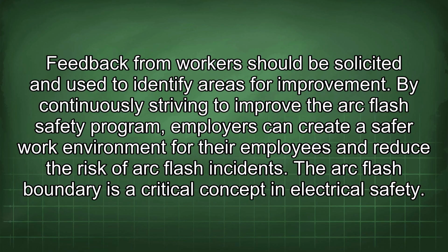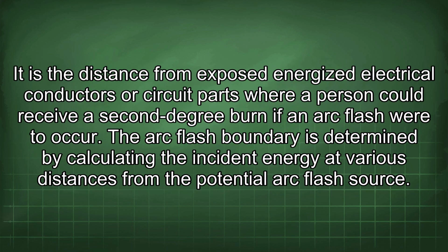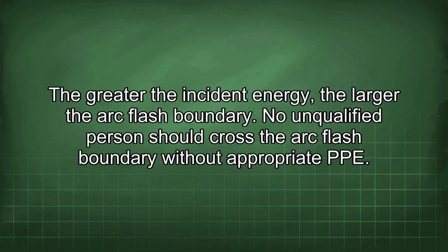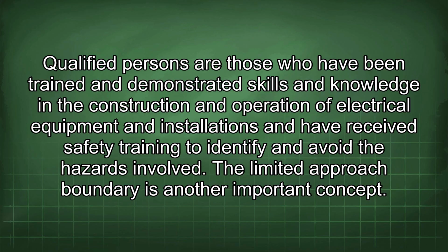The arc flash boundary is a critical concept in electrical safety. It is the distance from exposed energized electrical conductors or circuit parts where a person could receive a second-degree burn if an arc flash were to occur. The arc flash boundary is determined by calculating the incident energy at various distances from the potential arc flash source. The greater the incident energy, the larger the arc flash boundary. No unqualified person should cross the arc flash boundary without appropriate PPE. Qualified persons are those who have been trained and demonstrated skills and knowledge in the construction and operation of electrical equipment and installations and have received safety training to identify and avoid the hazards involved.